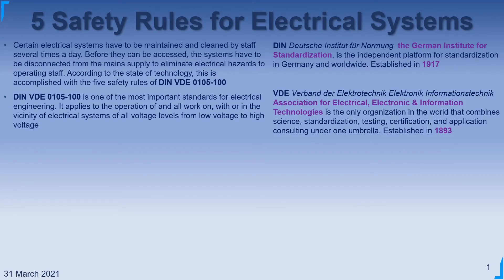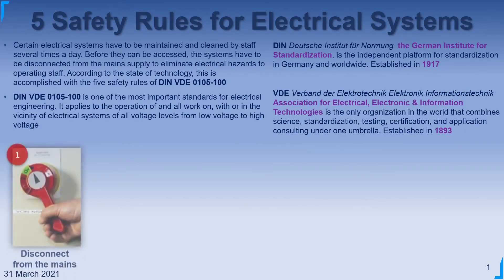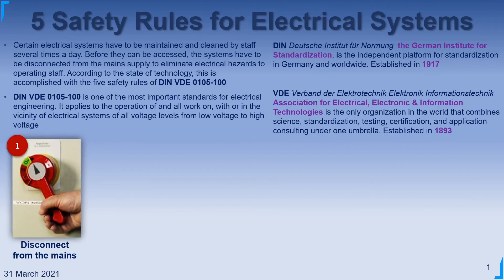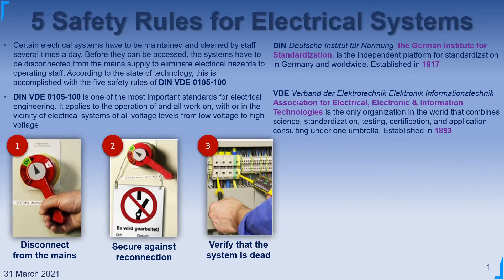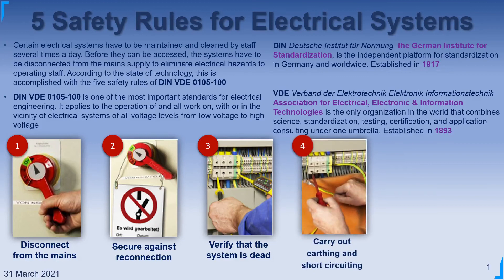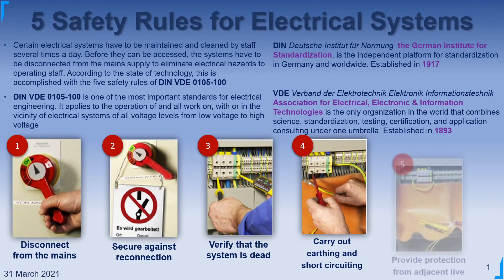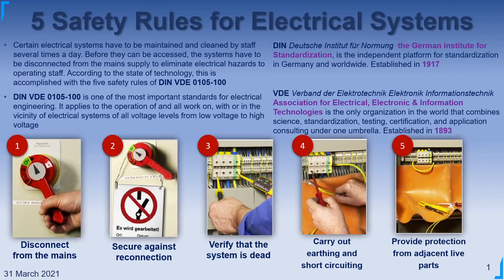Here are the five rules before beginning the work. Rule one: Disconnect from the mains. Rule two: Secure against any reconnection possibilities. Rule three: Ensure zero voltage, or verify the system is dead. Rule four: Carry out earthing and short circuiting. Rule five: Provide protection from adjacent live parts.